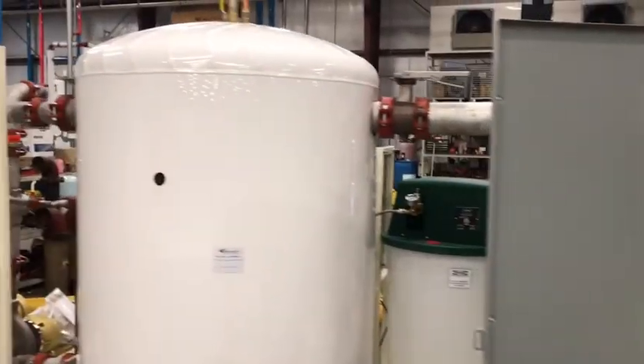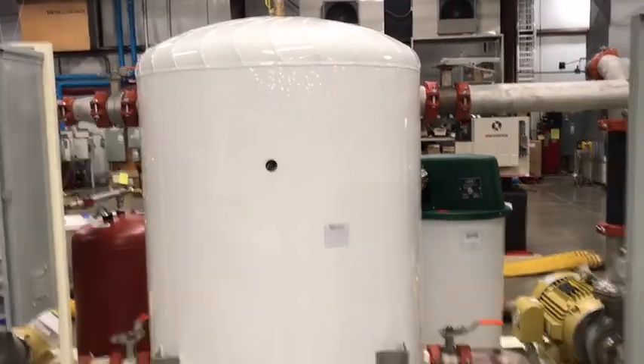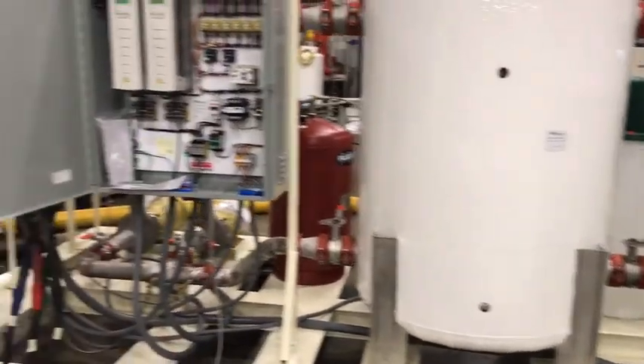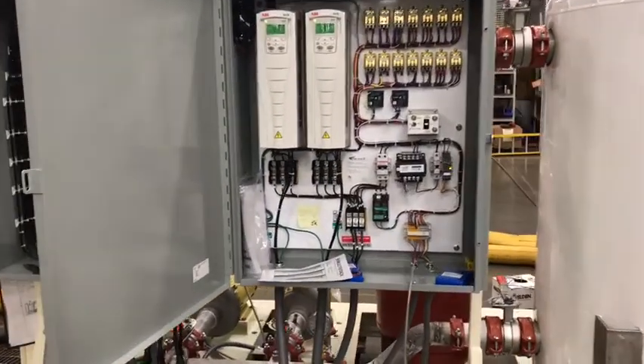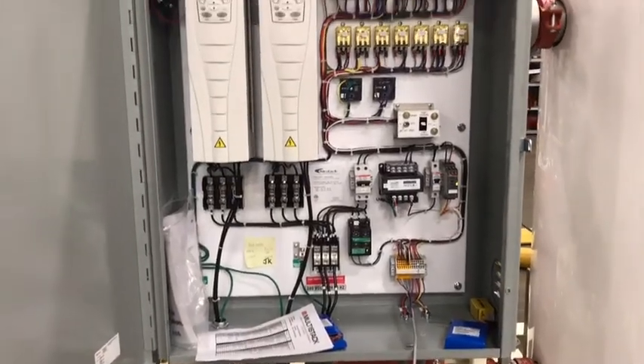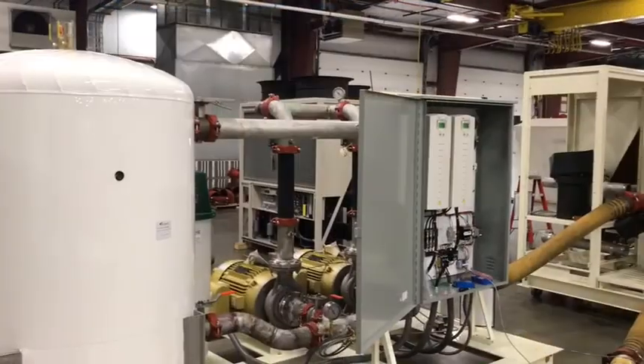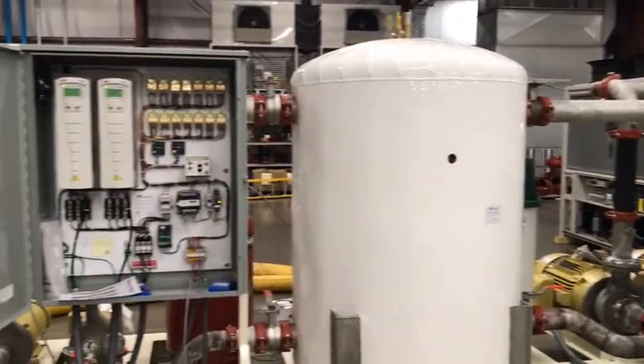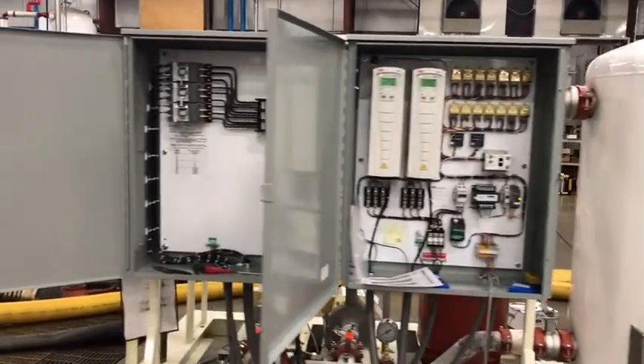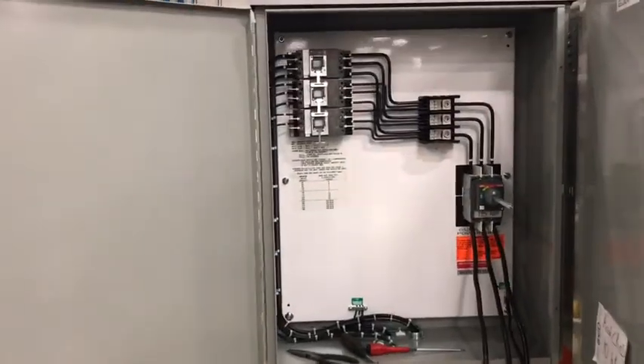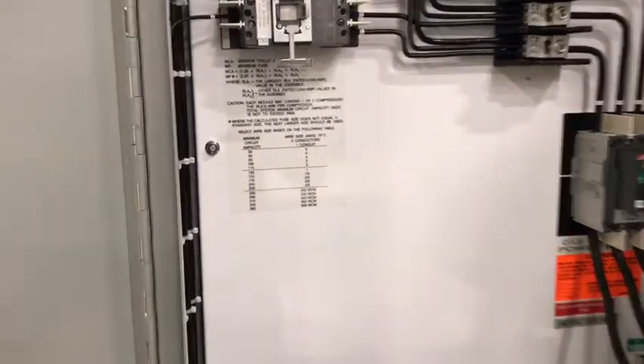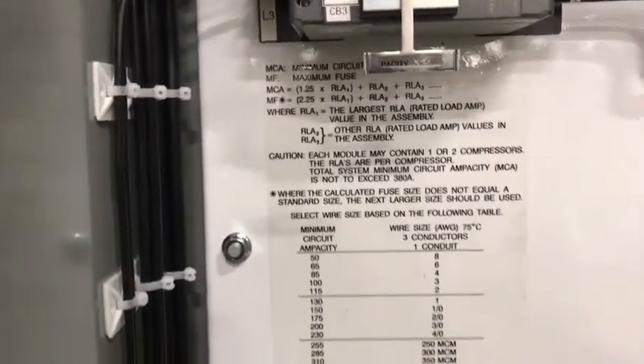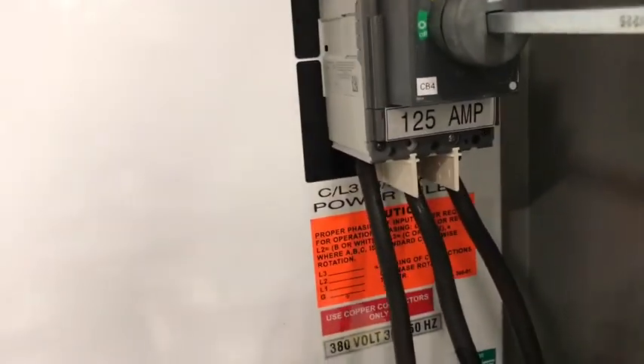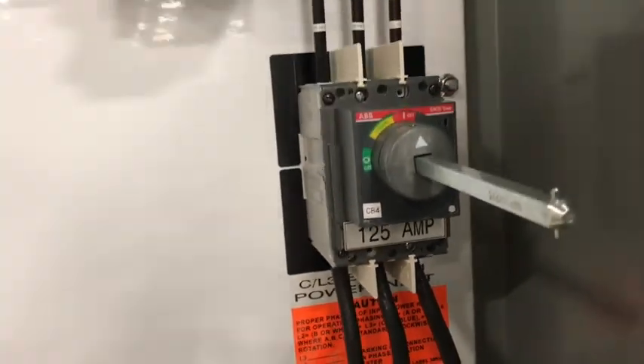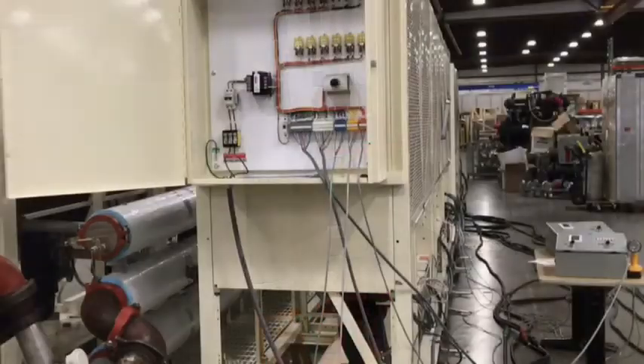So moving from that cabinet, we see the storage / decoupler tank in the middle. And then a similar identical cabinet for the pumps that are on the room distribution system. And then just a scan from right to left of the entire pump module. And this is the single point power connection where power for the entire skid, all 4 pumps, comes in here, through the door interlock disconnect switch, shown there, up through a power distribution block, and then over to 2 circuit breakers that feed each of the 2 pump VFD cabinets.